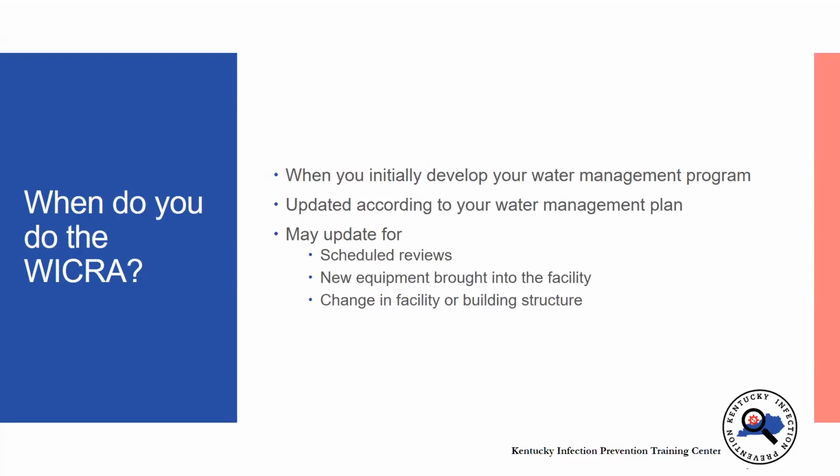You need to think about, what about when new equipment is brought into the building that requires the use of water? This can be something like ice machines, fluid warmers, something of the like. What about a change in the facility structure? Remediation, right? You have to go in and fix plumbing for some reason. You're going to do an addition to the facility. What impact does that have on your water system, and what needs to be done to mitigate the risk?